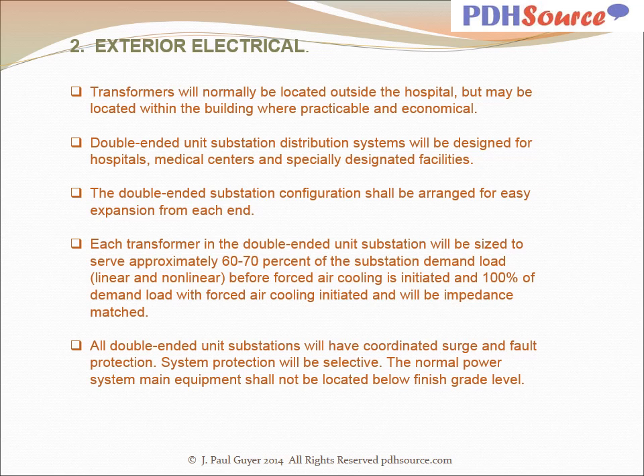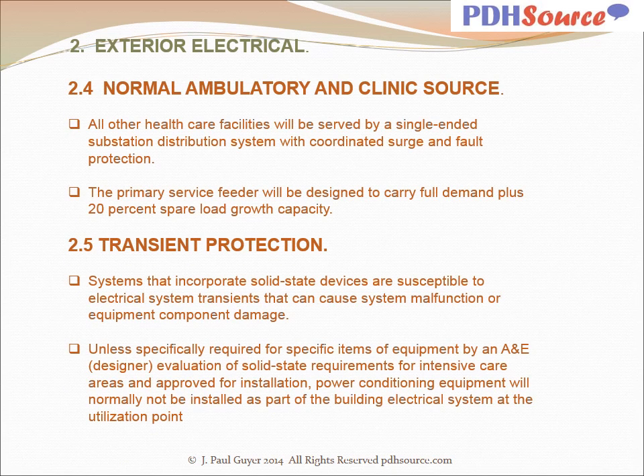All double-ended unit substations will have coordinated surge and fault protection. System protection will be selective. The normal power system main equipment shall not be located below finish grade level. For normal ambulatory and clinic sources, all other healthcare facilities will be served by a single-ended substation distribution system with coordinated surge and fault protection. The primary service feeder will be designed to carry full demand plus 20% spare load growth capacity.